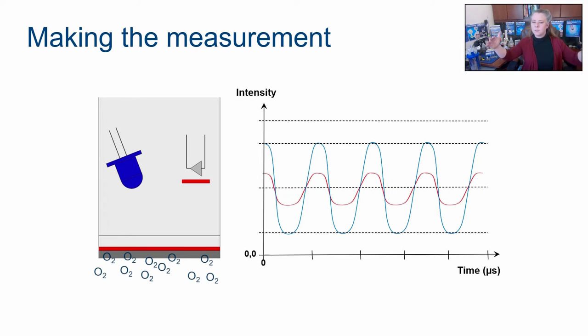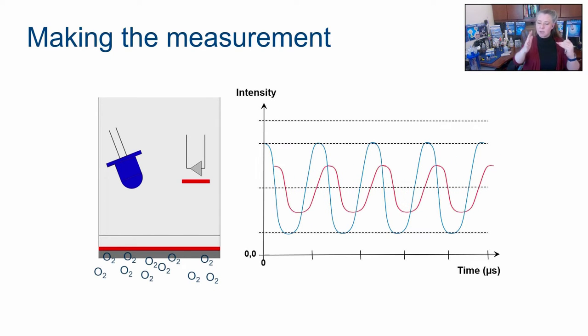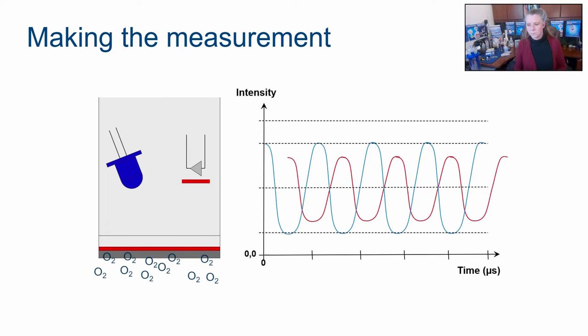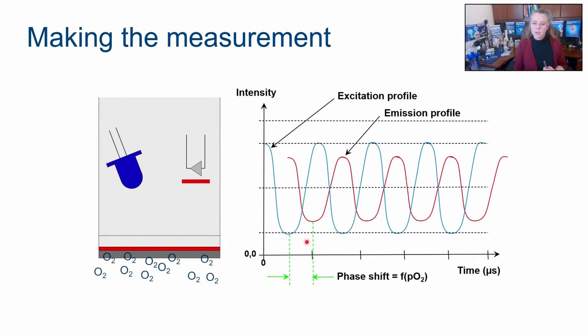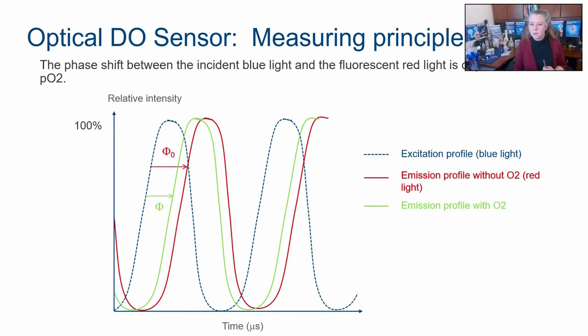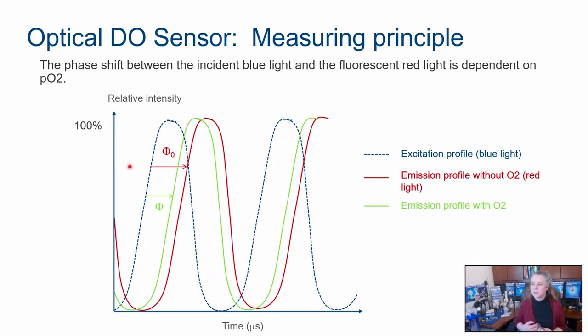When the oxygen gets involved, you see that red light shifts to a reduced intensity and a different wavelength. Okay. So how do optical oxygen probes measure? They actually care not so much about the intensity, but they care about the phase shift. This is where the initial light was. This is where the light with no oxygen was. And this is where the light with oxygen is. Blue light, green light is with oxygen, red light's without. You care about the phase shift. That phase shift is completely correlatory to oxygen.